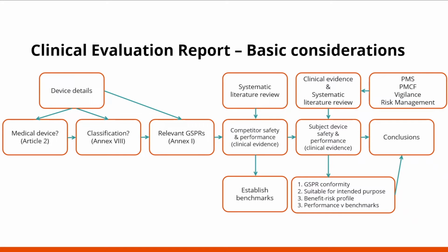So systematic literature reviews, both against competitor devices and also in relation to the subject device, are absolutely essential. But the other thing to remember is that outputs from post-market surveillance, post-market clinical follow-up, vigilance systems, and risk management systems all constitute clinical evidence or clinical data, and all of these must be considered in the clinical evaluation report.